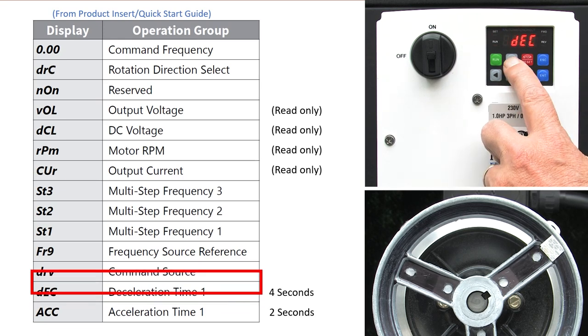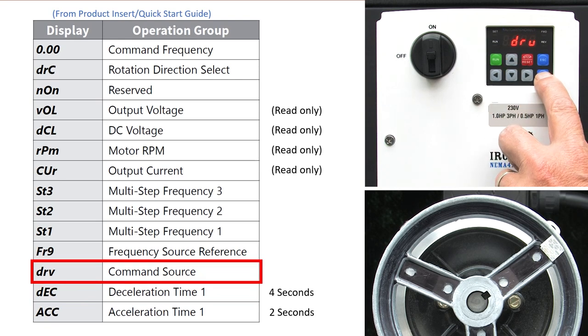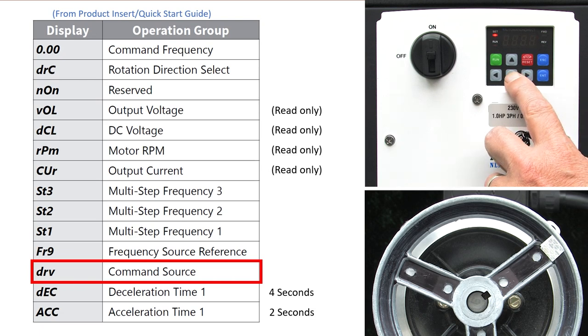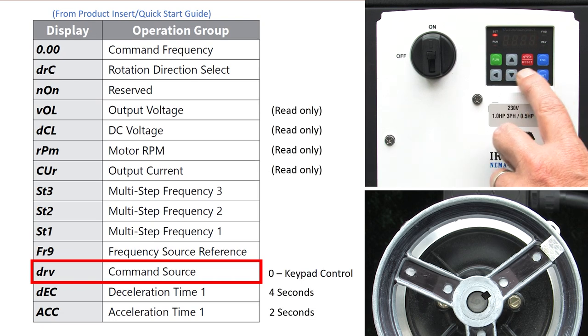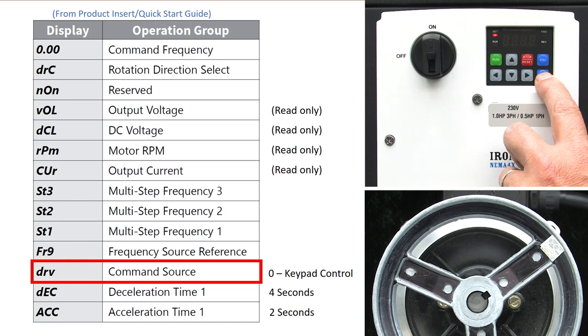I'll up arrow again to the drive command source selection. It defaults to a 1 which says use the input terminals for the drive run stop control. We want to use the keypad which is a zero. Enter to select that and again to accept it.